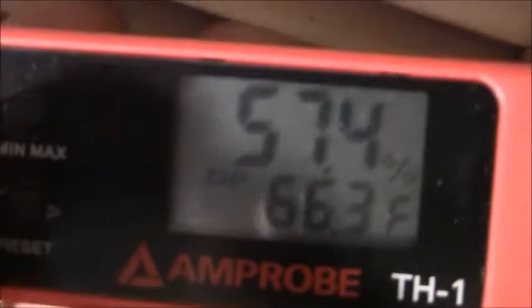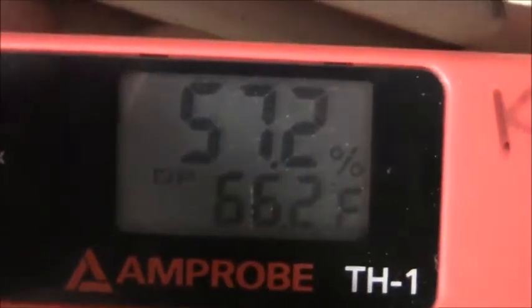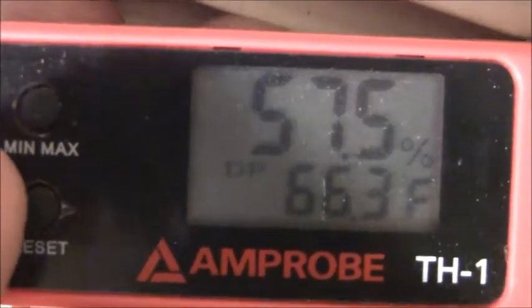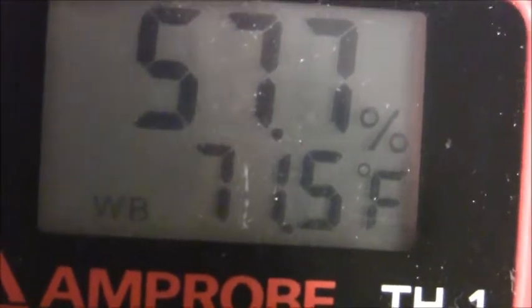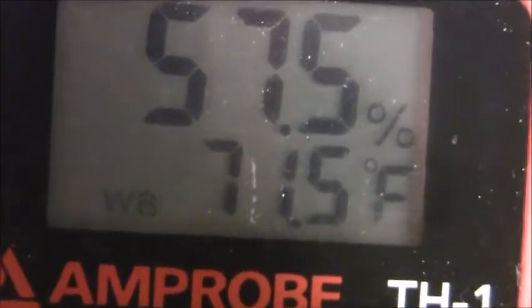By doing this, I have to hit the mode button right here and wait until that's the dew point right there. The dew point is 66. I don't want that. That's the wet bulb. That's what I want. So the wet bulb, 71.6. We'll call it 71.5. Oh wait, is it still dropping? 71.4. Hold on. Hold away slightly.